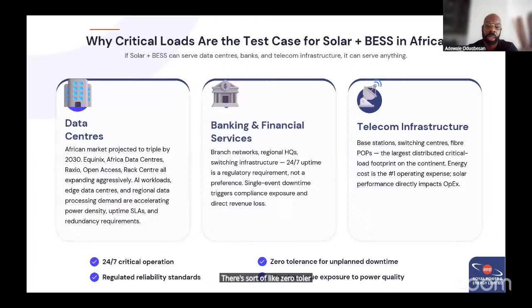There are three perspectives on every project: the OEM, the EPC, and the off-taker. The OEM is optimizing the product spec, the off-taker is optimizing operational outcome, and the EPC, which we are in this case, has to make sure these two things meet on site in real ambient conditions, with real grid quality, under operational constraints. Most project disappointments don't come from bad technology or bad clients. They come from these three corners of the triangle never quite aligning on the same operational envelope.